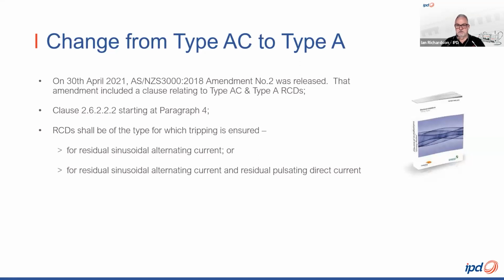So the clause 2.6.2.2.2 states that RCDs shall be of a type for which tripping is ensured for residual sinusoidal alternating currents, or residual sinusoidal alternating currents and residual pulsating direct current. So from what we spoke about on the earlier slide, we can see that a type AC complies with the first part of that requirement, but not the second part.